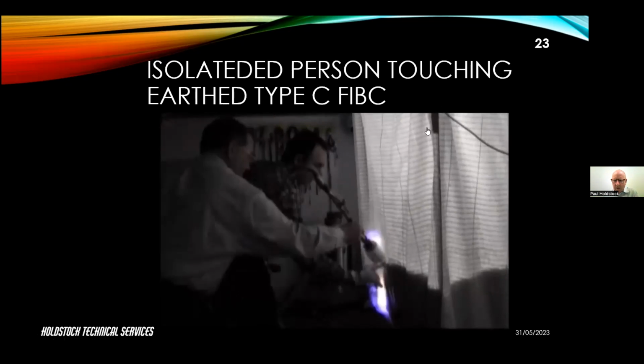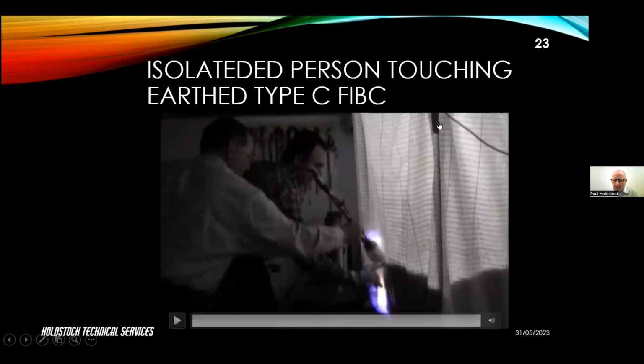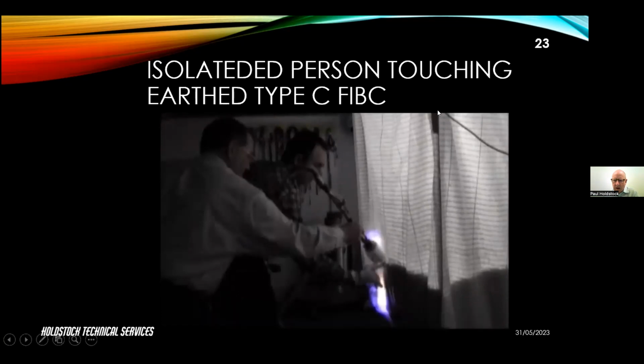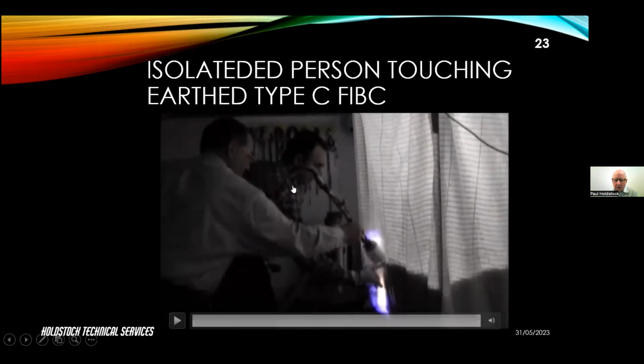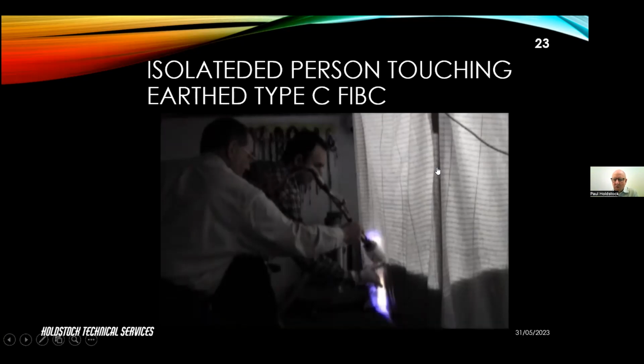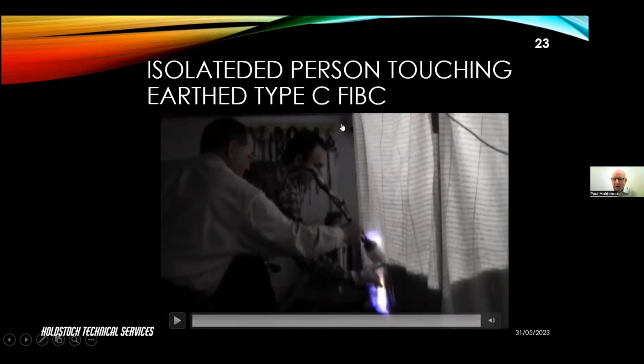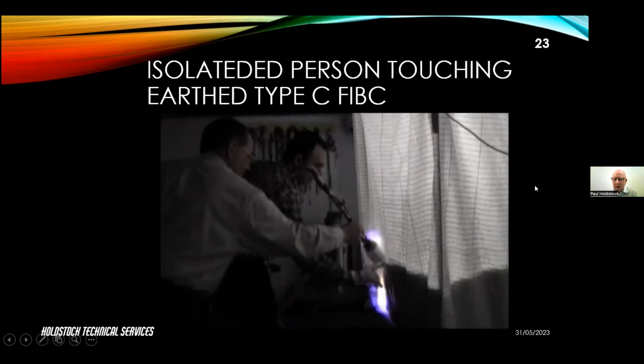Okay, so you can see there, this is the Type C FIBC. You can see the grid of conducting threads, and this is the earth bonding cable. You can see now that a charged isolated person touching that bag when there is an explosive atmosphere in the area will cause an ignition. So just because the bag is earthed doesn't make the whole system earthed. Just because the bag is earthed, it doesn't mean that the whole system is safe. We still need to pay attention to nearby conductors.